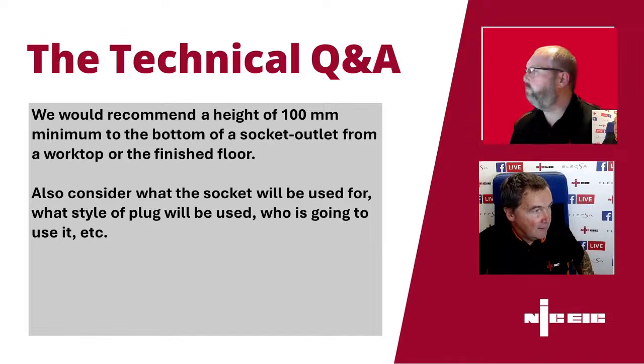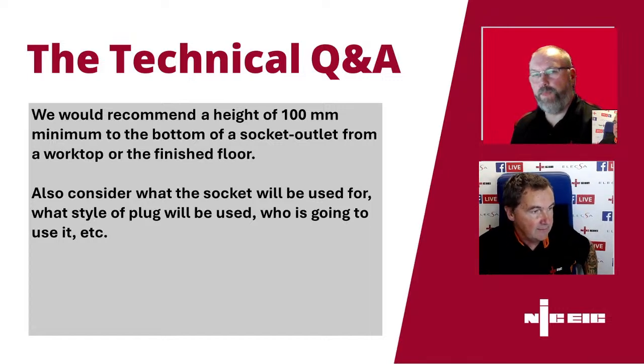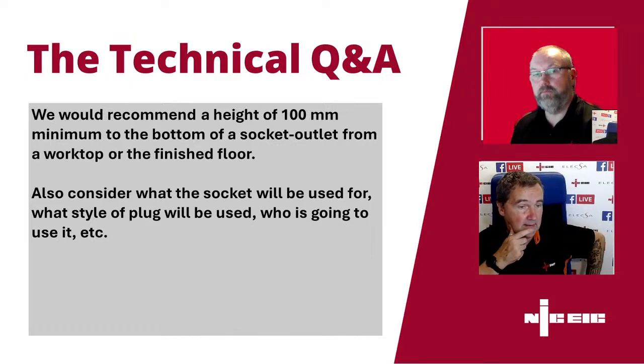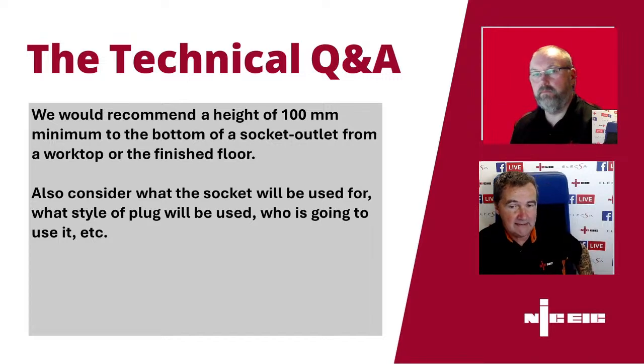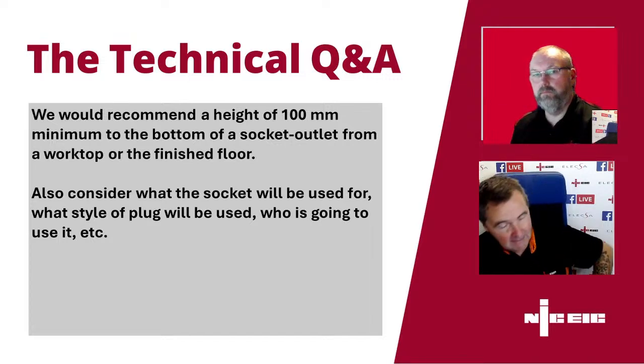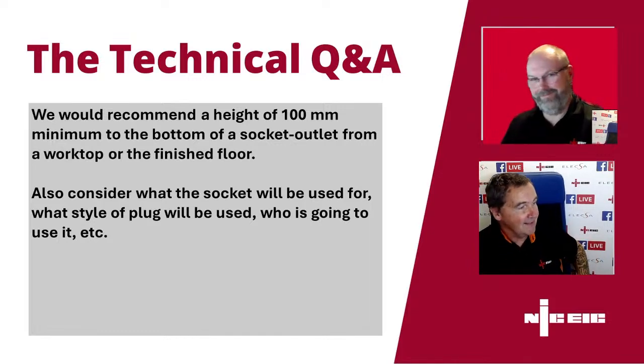One of the engineers has commented that the 100 mil from the socket and worktop would also be dependent on if an upstand was fitted. The height would need to be increased if an upstand was fitted. So when we talked about that, in general we recommend 100 mil, but you do need to consider what the socket outlet is going to be used for, what style of plug, who's going to use it, etc. We can all remember back to the days when people were putting socket outlets on skirting boards and it was extremely low and just about unusable. So that's where that 100 mil has come from, to take us above that.